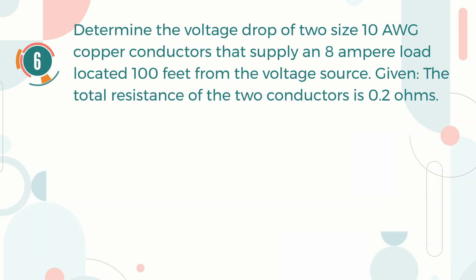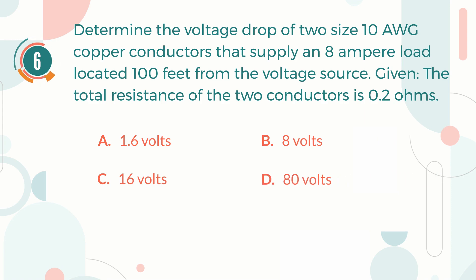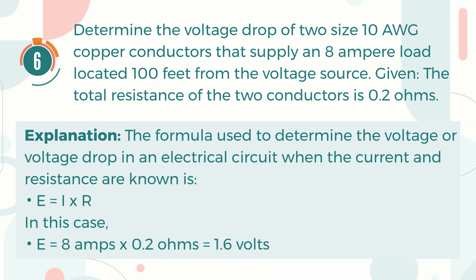Number six: Find the voltage drop of two size 10 AWG copper conductors that supply an 8 ampere load located 100 feet from the voltage source, given the total resistance of the two conductors is 0.2 ohms. A) 1.6 volts. The correct answer is A, 1.6 volts. The formula used to determine voltage drop when current and resistance are known is: voltage equals current multiplied by resistance. In this case, voltage equals 8 amperes multiplied by 0.2 ohms, which equals 1.6 volts.